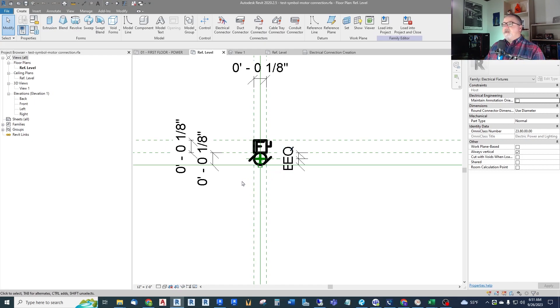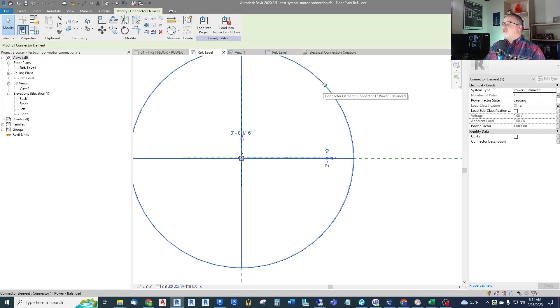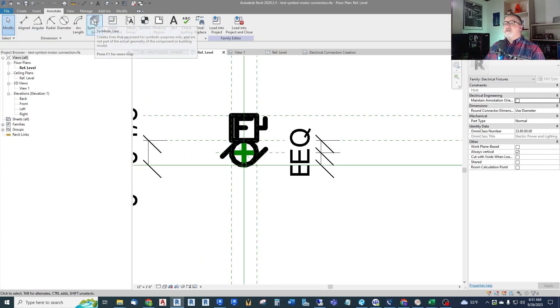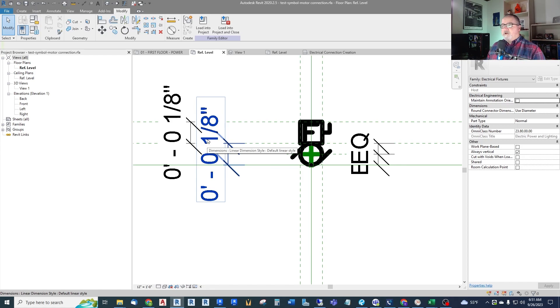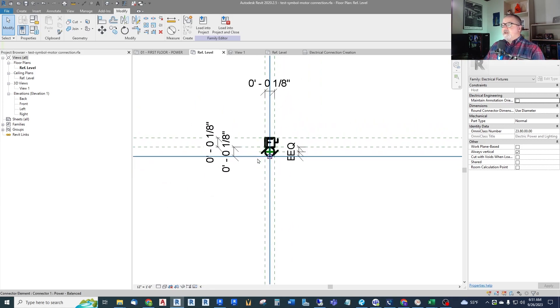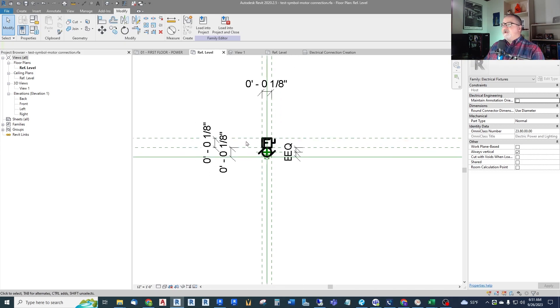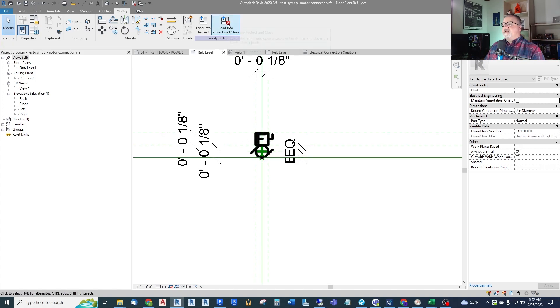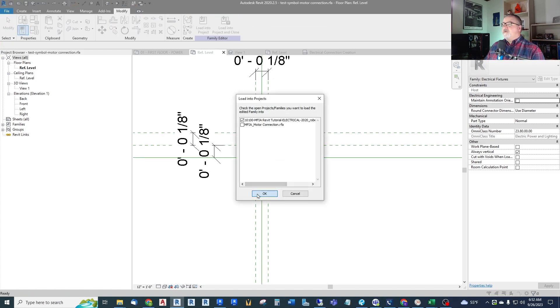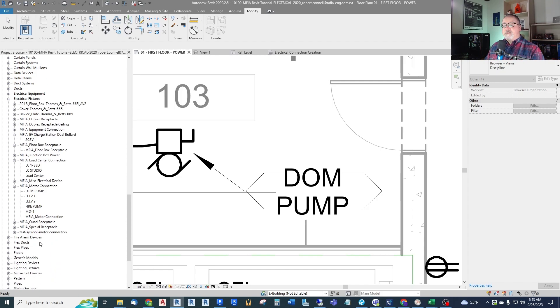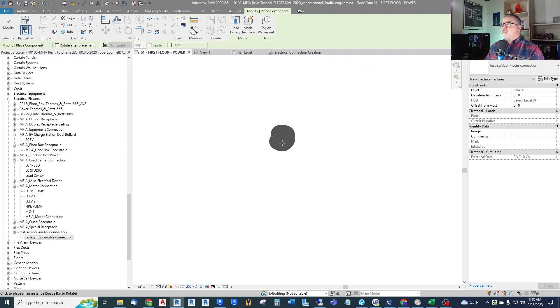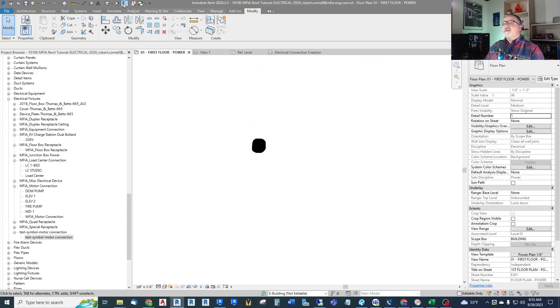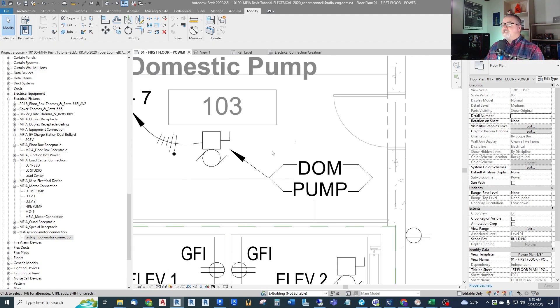So here is one that I made that is just an electrical fixture from the electrical fixture template, and I've put in the electrical connection right here, connector element, for the electrical information. I've gone ahead and drawn in with symbolic lines, the symbol. As you can see, it's a very thick line because I'm drawing it at actual what you might call paper or sheet space dimensions, actual dimensions for a symbol of eighth inch circle, eighth inch square with the fuse indicator. And so I've done that to show you that when I bring this into my model, it ends up thinking that it's actually an eighth inch by eighth inch physical device inside my model rather than a symbol. So let me bring that symbol in. I'm going to load this into my tutorial project. I have it in here as just a test. So let's go to our electrical fixtures, and we will find this little test symbol. So I bring this in, and first of all, you can see I have to zoom way in. It looks like a blob. I'll put it in here, and I'll turn on the thin lines property so I can see it. Well, there it is. However, again, it is only an eighth of an inch. So in my model, it is microscopic. You can't see it.